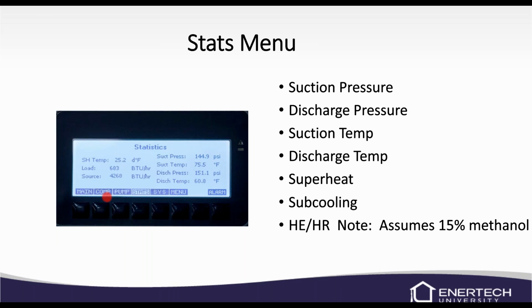Stats menu, in the stats menu, it's going to show you your superheat temp, your load and source BTUs, which may not be real accurate, your suction pressure, suction temperature, discharge pressure, discharge temperature. Now, we assume on the HE and HR on the source, don't really pay a whole lot of attention to the load. That's going to bounce around quite a bit based on the loads that are available, or that are in use. But the source is the heat of extraction and heat of rejection, and they're using 15% methanol. So if you have a different type of antifreeze, your heat of extraction or rejection could be a little bit different.